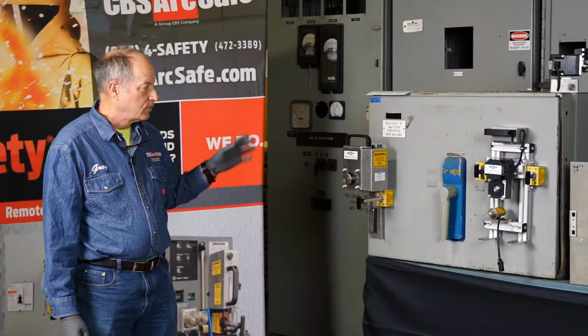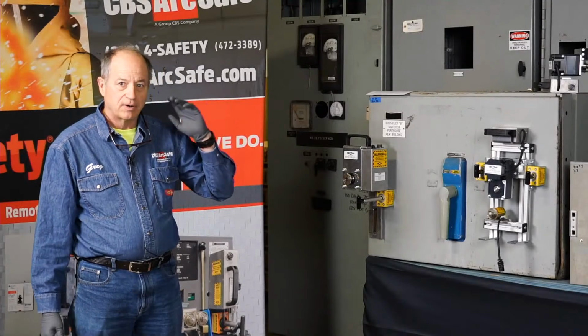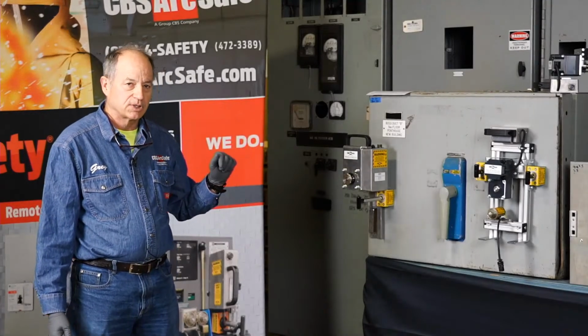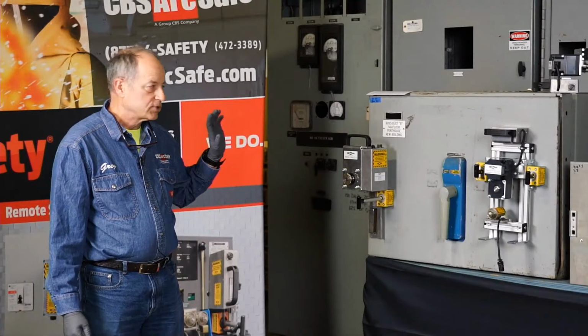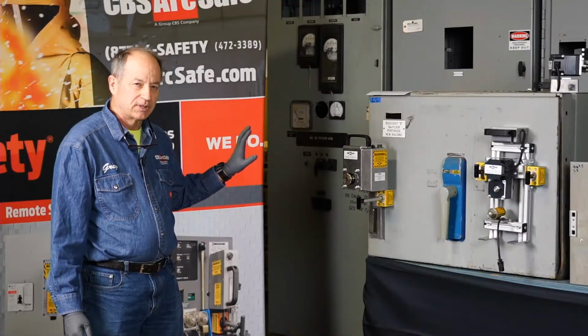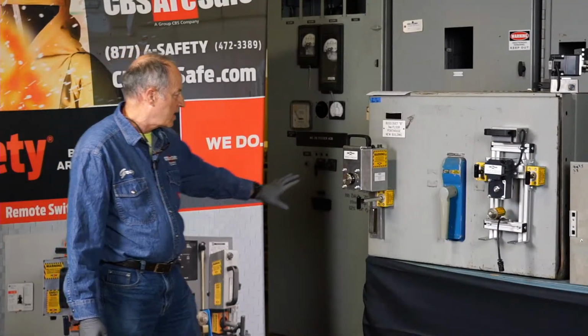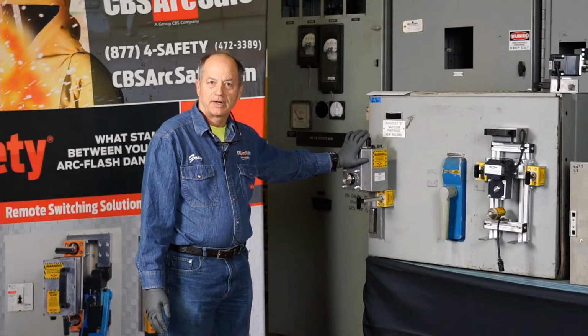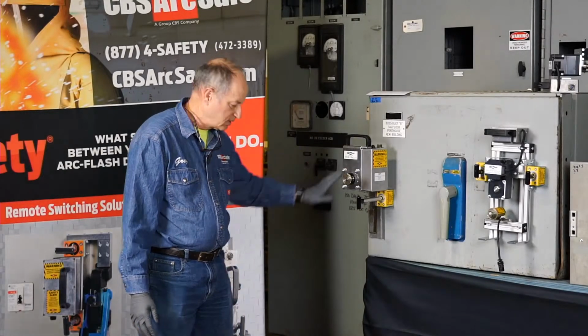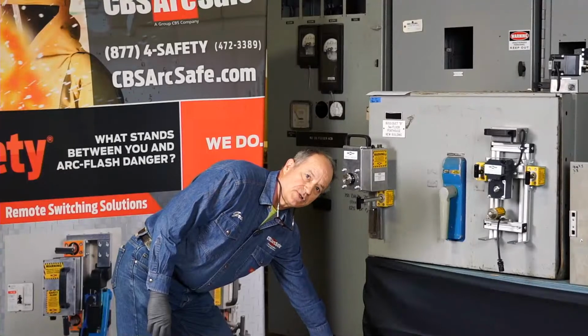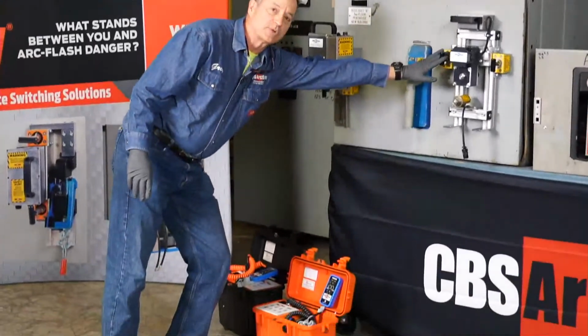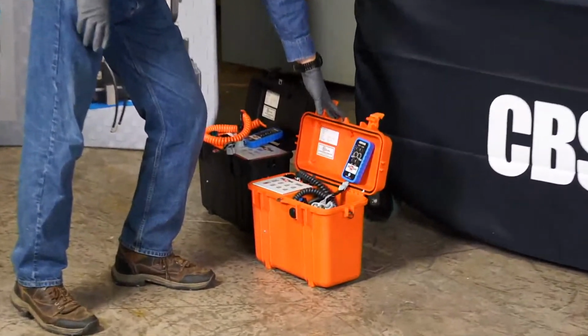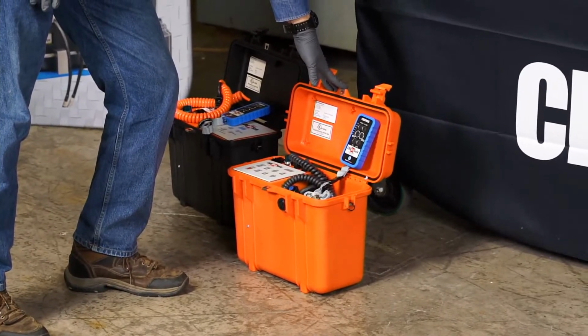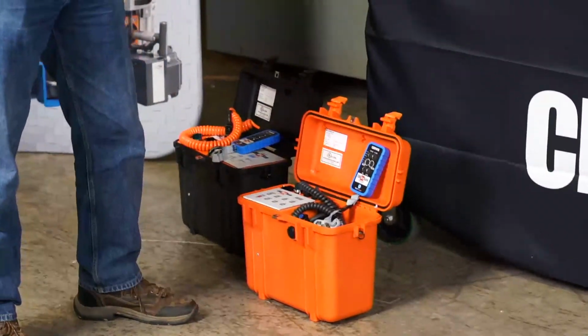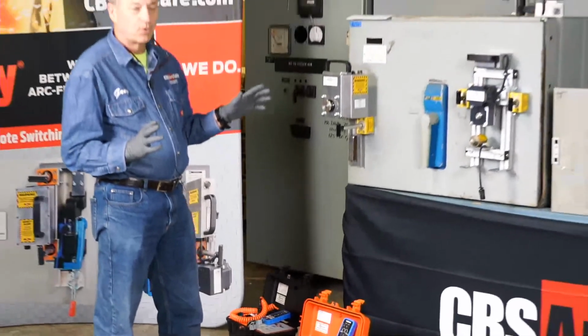Anytime we're working with a breaker, we need to get our nomenclature correct, so we refer to task-specific items. Remote racking is getting a breaker on and off the bus. Remote switching involves remote switch actuators and remote switch operators. So this is a remote switch actuator, and here's a remote switch operator, okay — it comes in a task-specific form.